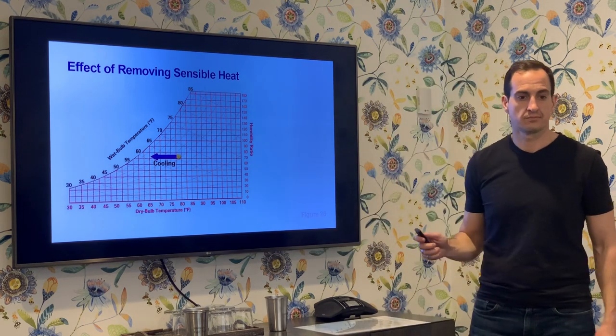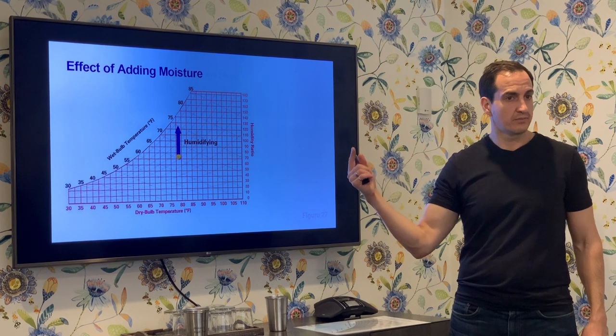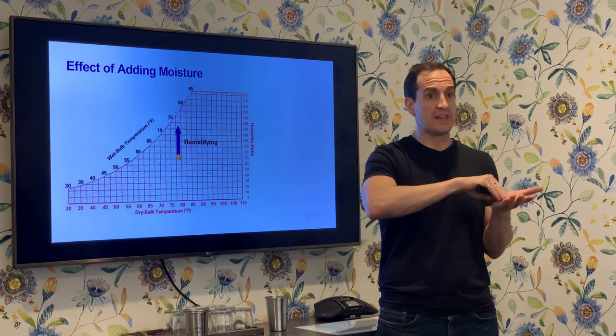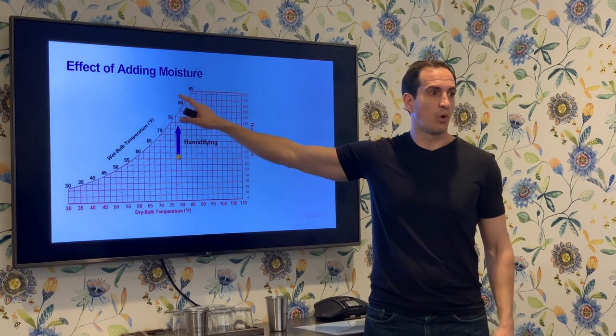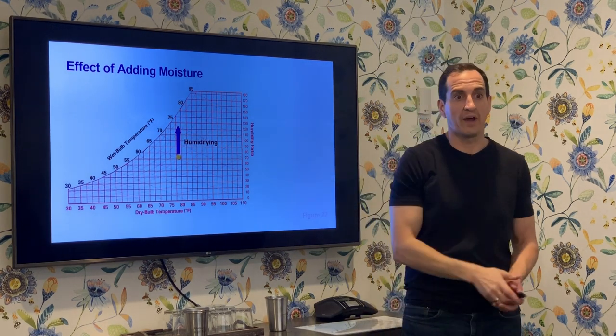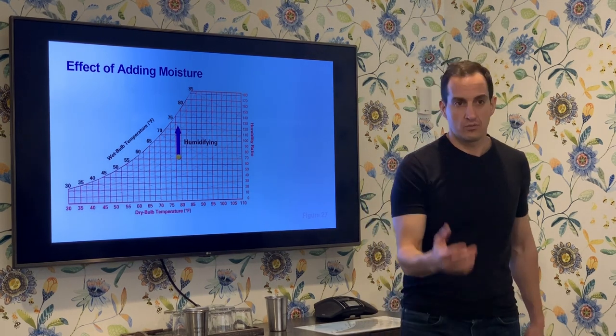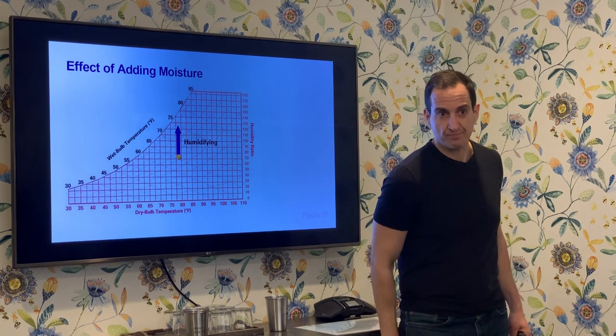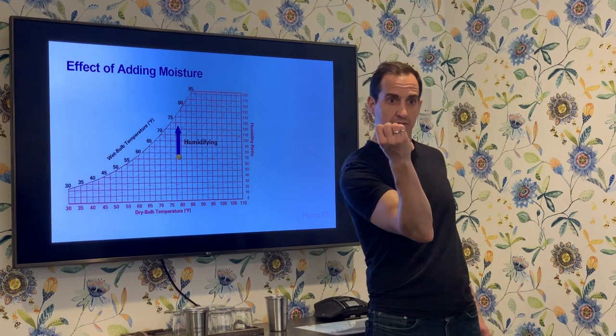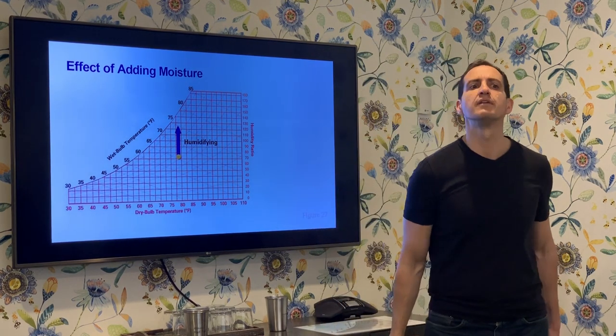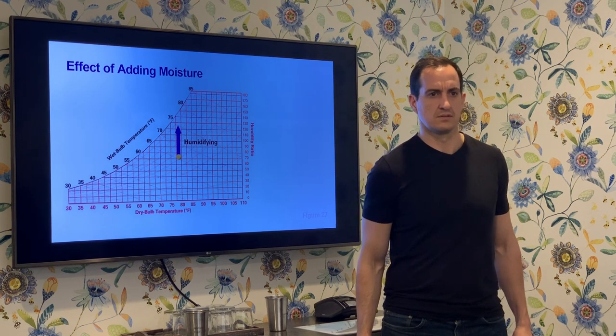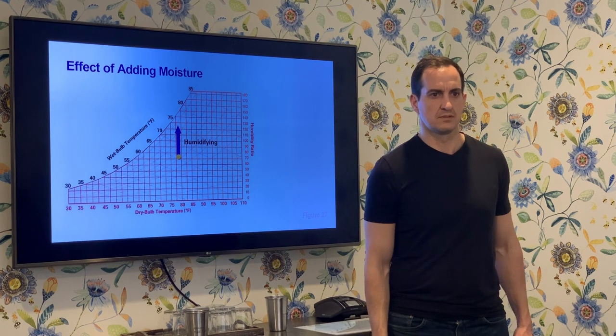I can add moisture directly to a space, but it's actually harder than you might think. Going from the current room temperature and humidity straight up on the chart toward the intersection of dry bulb, dew point, and wet bulb is quite hard to achieve. As I add moisture into the air, it gets colder — why? Because of evaporative cooling: a droplet of water as it evaporates absorbs sensible energy from the space, and those water molecules shed off the droplet until it is fully evaporated into the air.